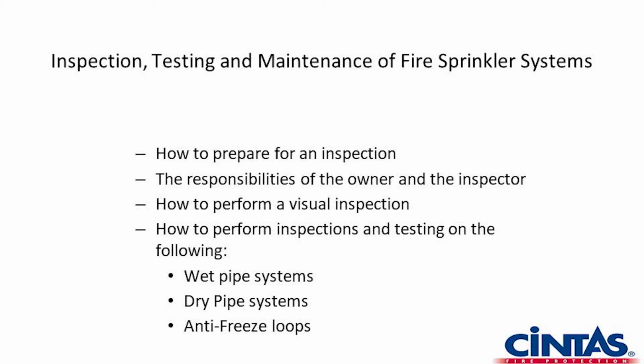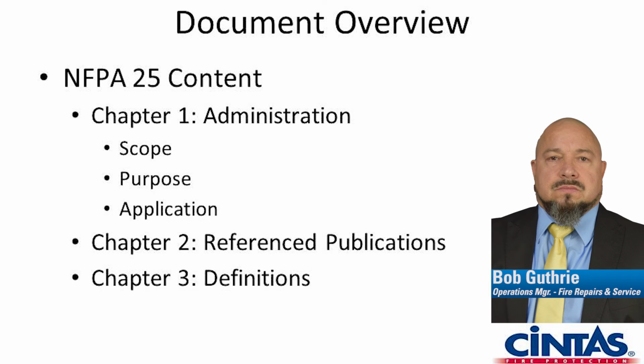We'll be covering some things: how to prepare for the inspection, the responsibilities of the owner and the inspector, visual inspections, and then inspections specific to wet, dry, and antifreeze system inspection. Just about all NFPA documents are laid out in a similar way, at least through the first 4 chapters. It starts with the administration, which will cover the scope of the standard itself, the purpose, and what application should be used when you are applying the rules and regulations of NFPA 25 or the related standard.